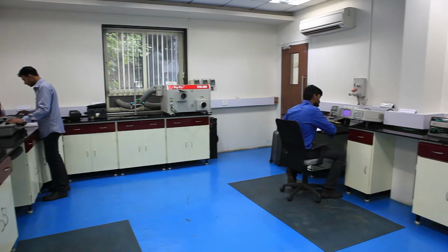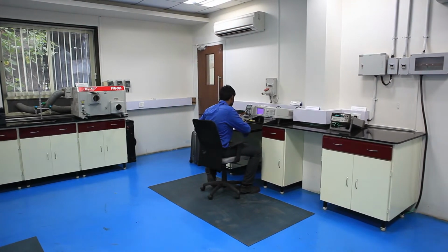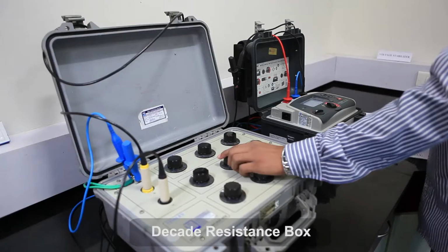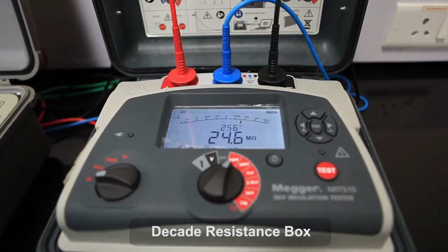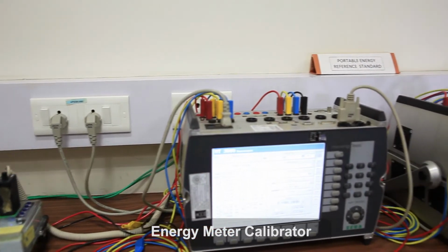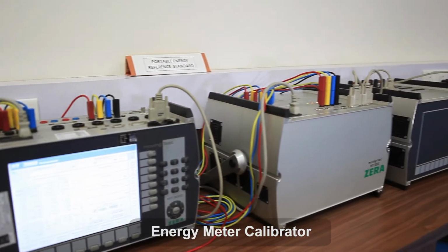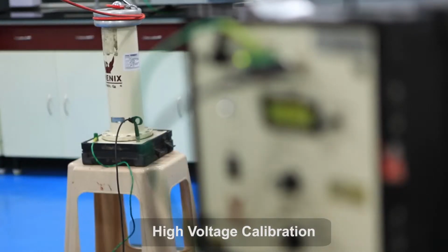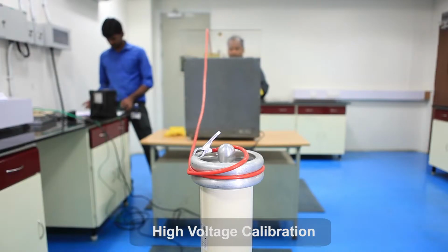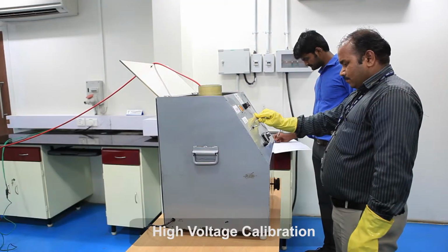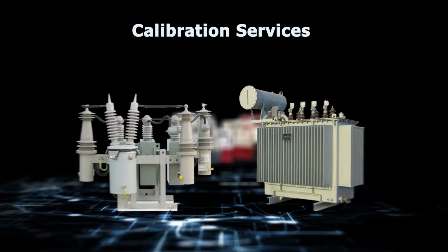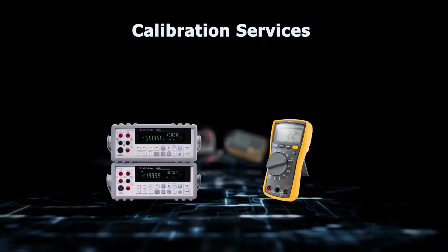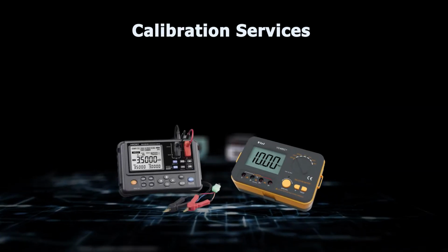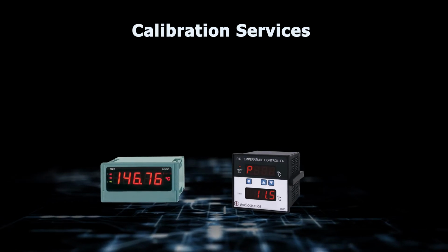ERDA West has NABL accredited facilities for carrying out calibration of electrotechnical parameters at laboratory as well as on-site. The major calibration services offered include high voltage calibration, CTPTs, energy meters, power meters, multimeters, micro-ohm meters, and temperature indicators.